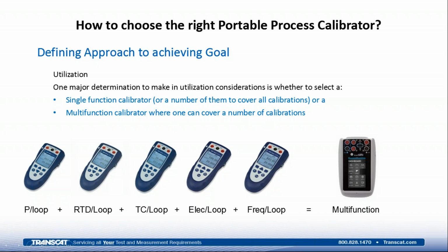So one of the major determinations in selecting a process calibrator is they come in two primary categories. One's a single function calibrator that'll do one or I guess a couple of things, versus a multifunction calibrator where you have one calibrator that can do all of the parameters that we discussed before: electrical, temperature, pressure, frequency, pulse count, etc. So each approach has, again, its advantages and disadvantages. If you have single function ones, you can deploy those for specific calibrations. For example, if you have a lot of RTDs that need to be done, you can deploy just the RTD and loop calibrator, or thermocouples, or any one of the individual ones, while another technician or operator could be using one of the other instruments.